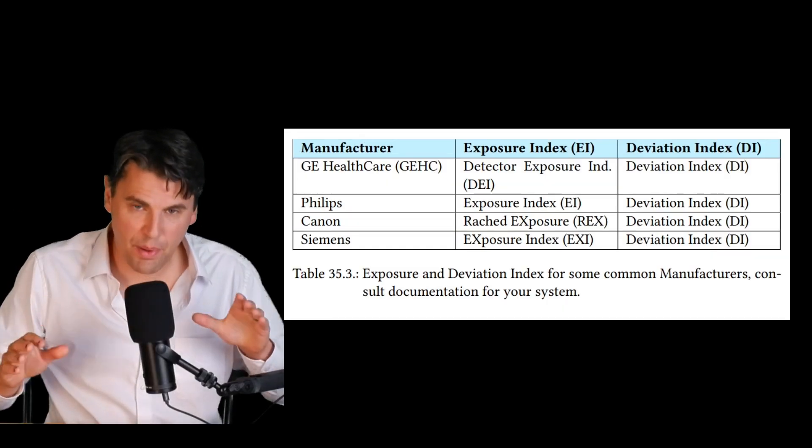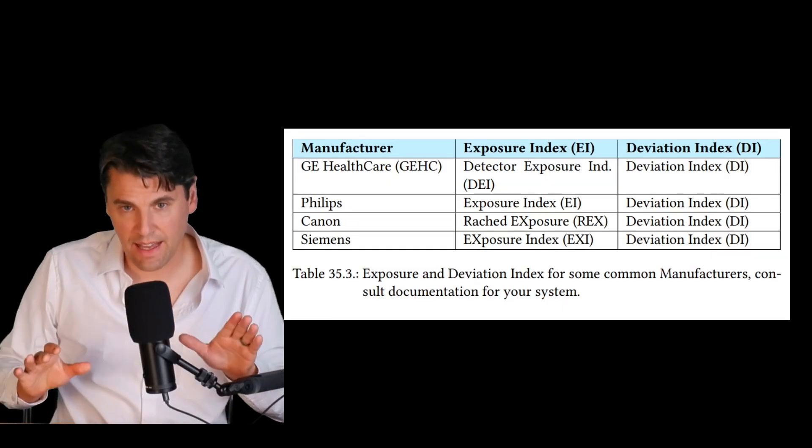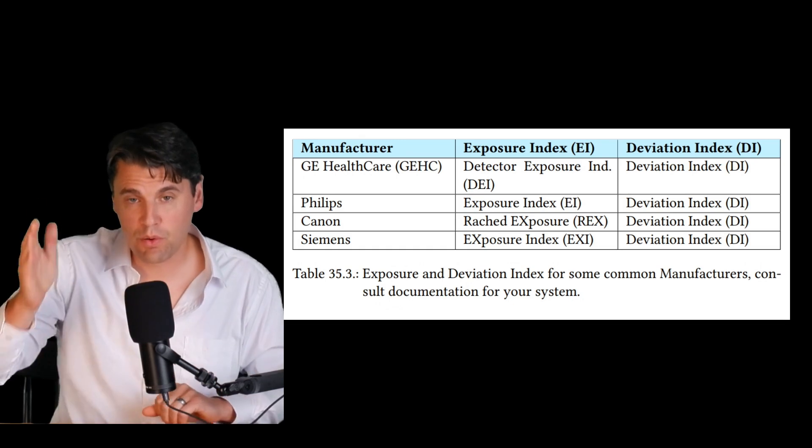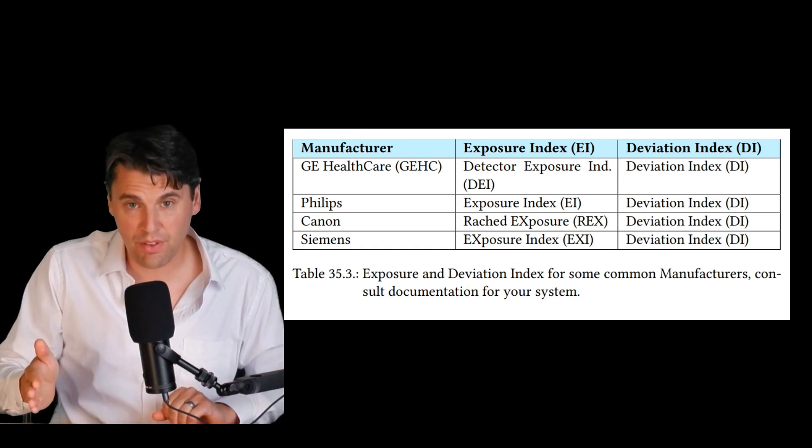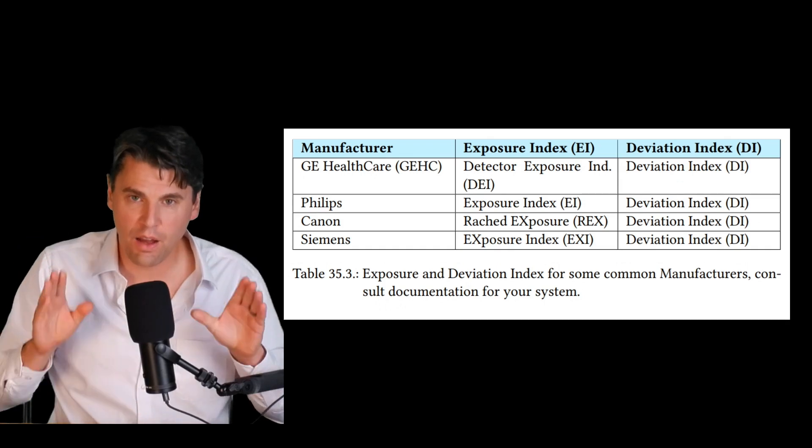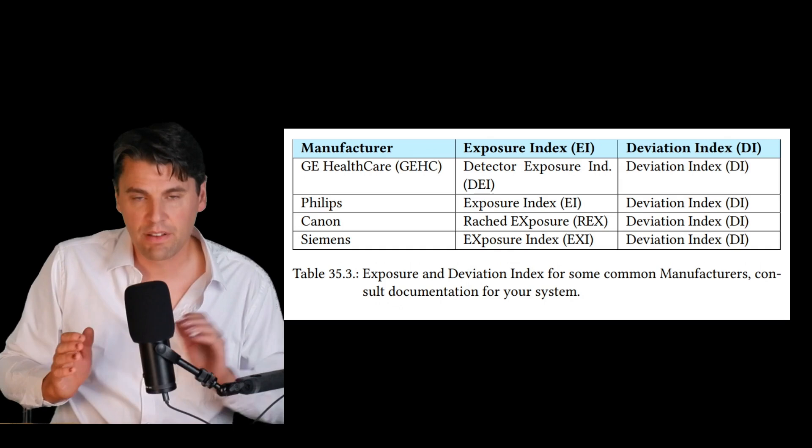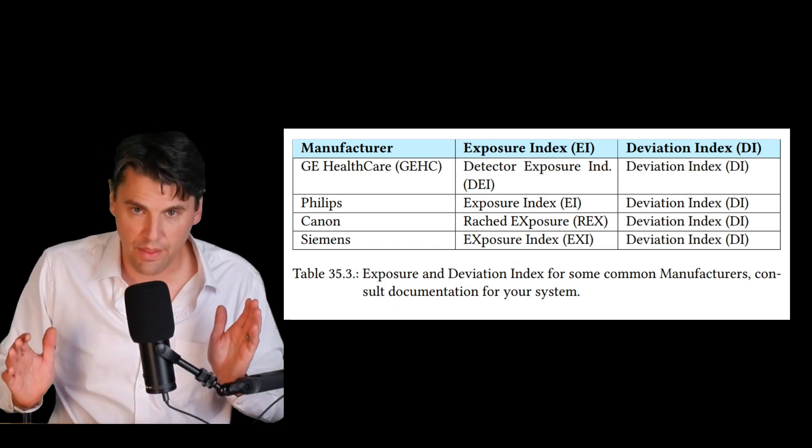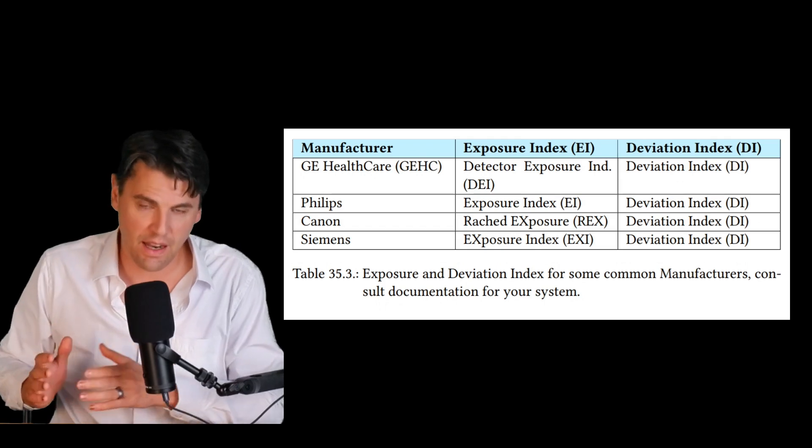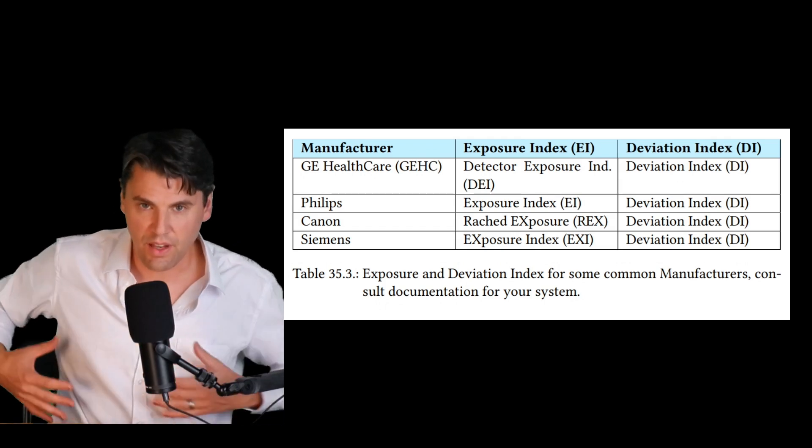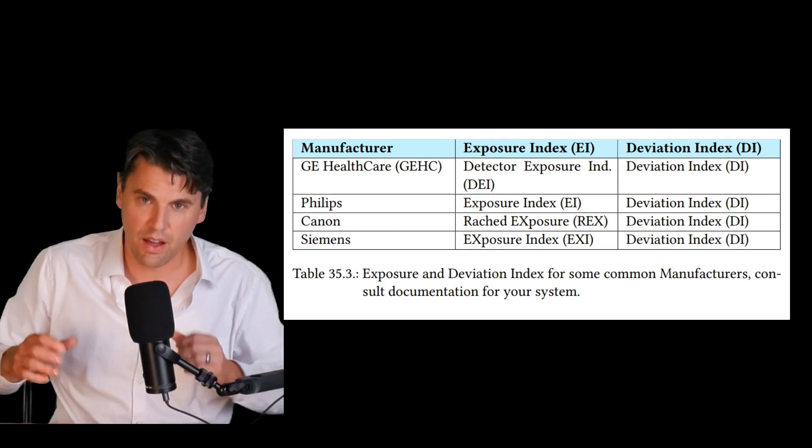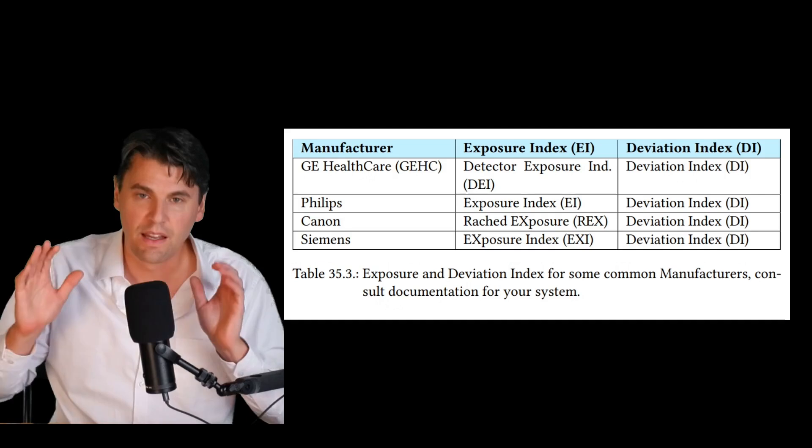One thing to keep in mind, we call this exposure index. Again, it's the exposure at the detector or the image receptor. It is not a measure of the radiation dose directly in the patient. Obviously, it typically correlates with, but it's dependent on lots of other factors such as the habitus of the patient, the kVp.